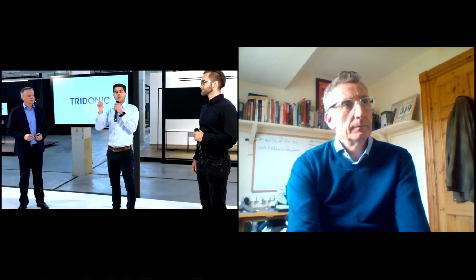And inside the luminaire, how does it look when you put the BasicDim Wireless devices in the luminaire? Yeah, so this is something Elias has shown in our live setup and in our first presentation as well. Inside the luminaire, you have the possibility to use an active module. Active module means that the module has an internal power supply, and this internal DALI power supply supplies power to the DALI driver.